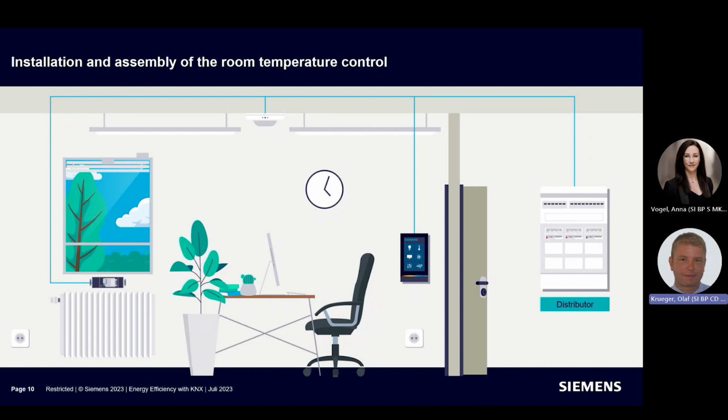The room control unit TC5 is usually located in the entrance area of the room, next to the door. The presence detector is mounted on the ceiling in a good detection area of the workstation. For the thermal drive actuator, the modular version RL605D23 is used in this example. This can be installed with the control module box AP118, which is available as an accessory for decentralized installation in a cable trunking under the window.